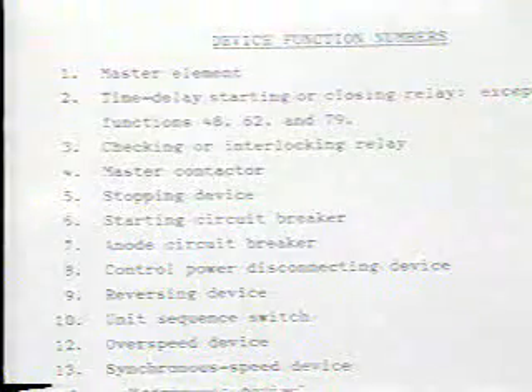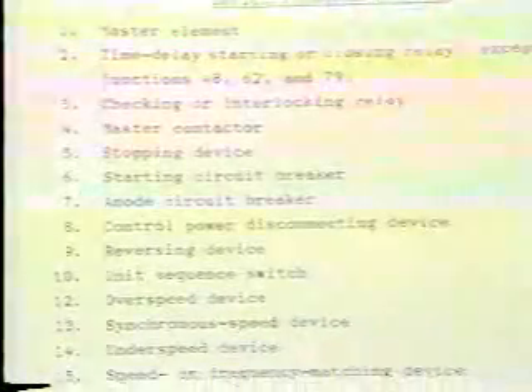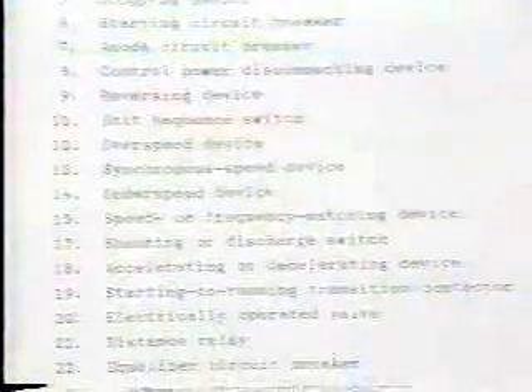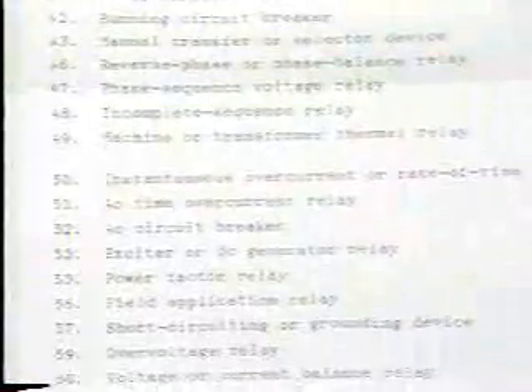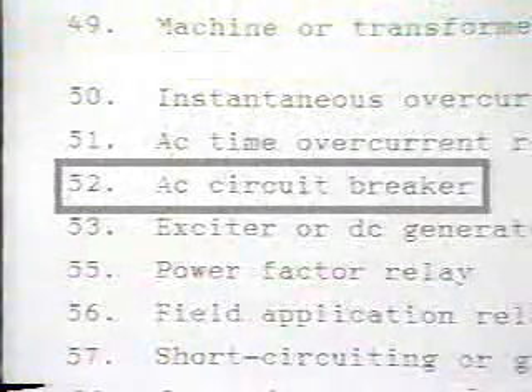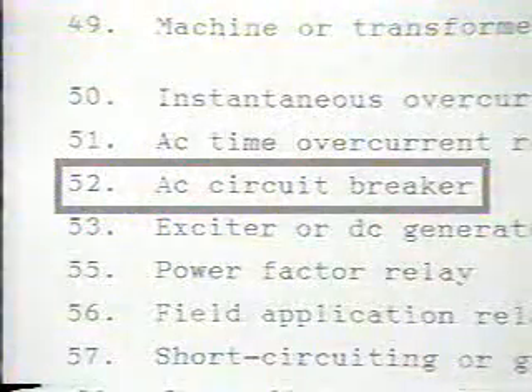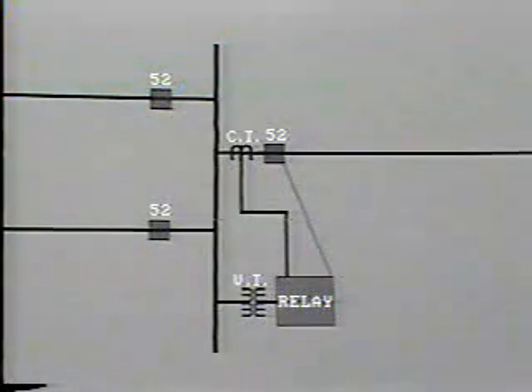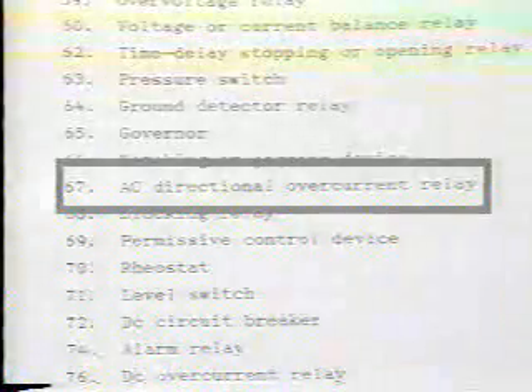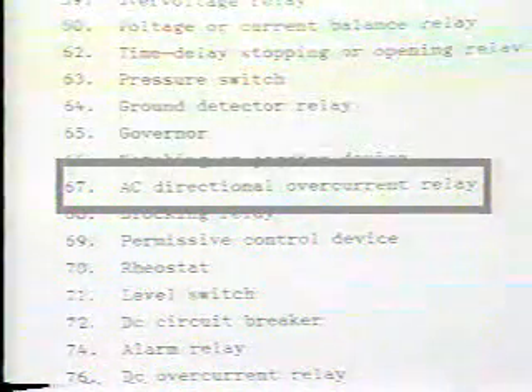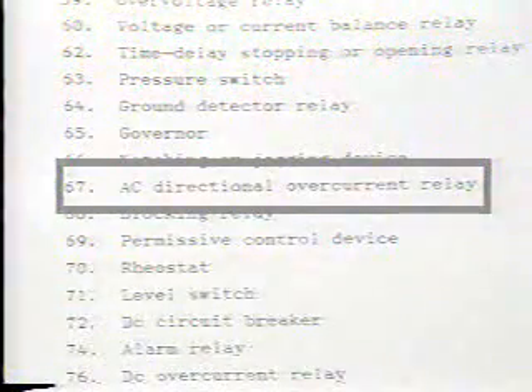The list is quite extensive, numbering from 1 to 94. For example, quickly running your eye down the list, we find a master contactor, synchronous speed device, distance relay, field circuit breaker, AC circuit breaker, ground detector relay, rheostat, frequency relay, line switch, and so on, all with their respective numbers. The circuit breaker is represented by number 52, so we can place this into our elementary diagram. And supposing the protection relay is an AC directional overcurrent relay, this would be device number 67.